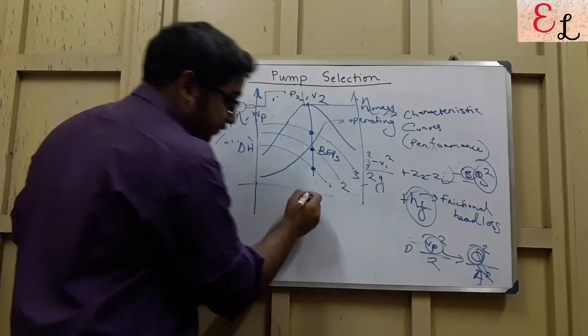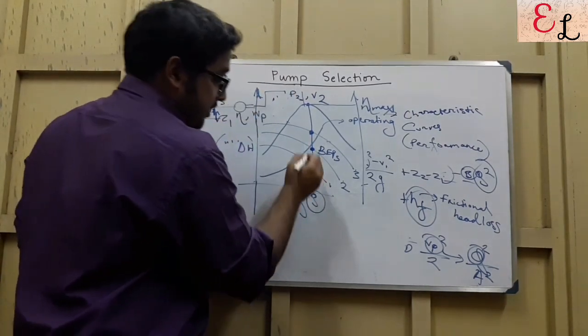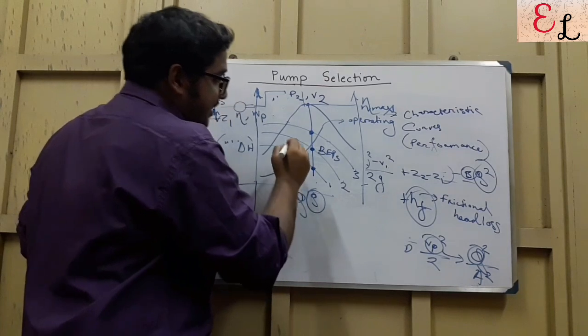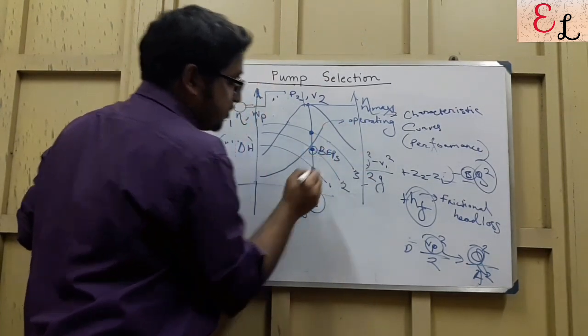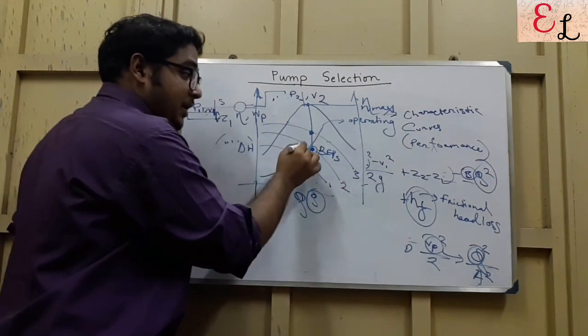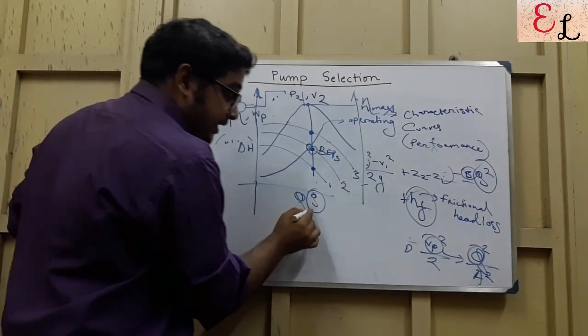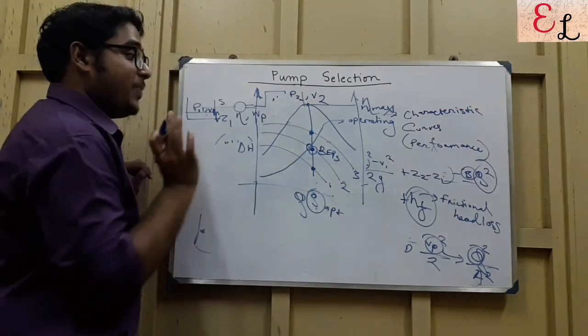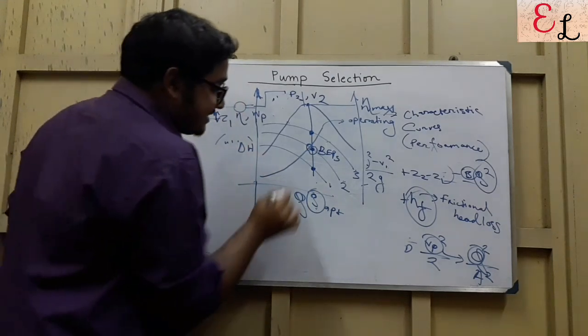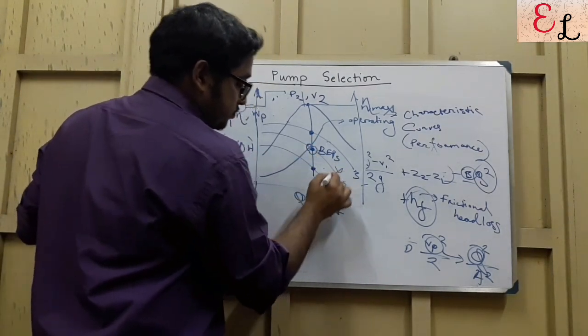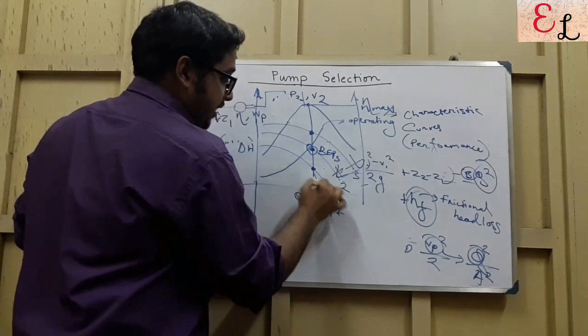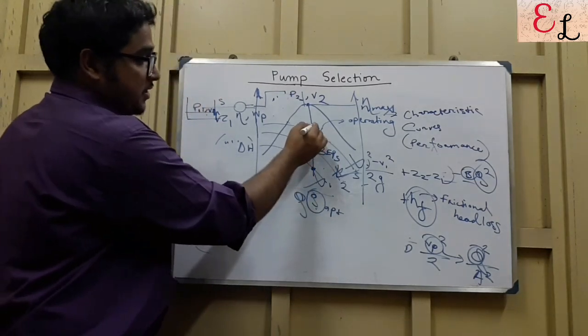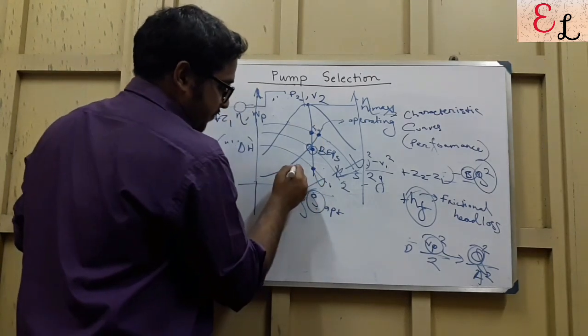These three points are my BEPs, because this is the maximum efficiency. If we drop them to the characteristic curve, we see these are the maximum efficiency points. So these are the operating points, the flow rate at which it attains maximum efficiency. We see that the operating curve is closest to this point. For the second pump, the operating curve is cutting a point wherein it is closer to the Q optimum, the Q that should have been there for obtaining maximum efficiency, the best efficiency.